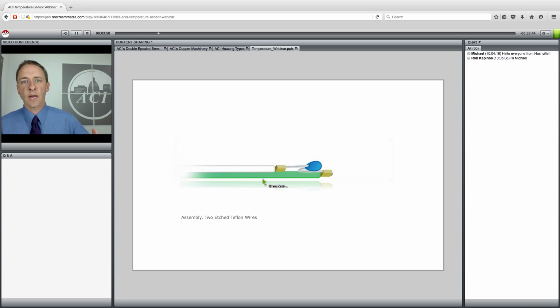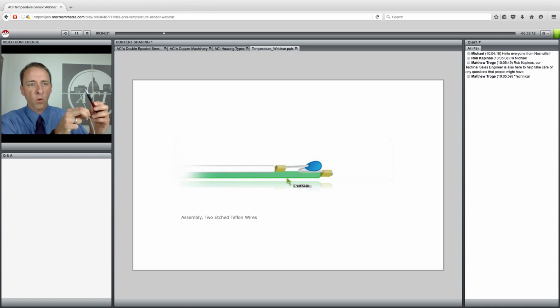And we also use a higher grade lead wire. It's an etched Teflon lead wire, compared to what a lot of other people are using, which is PVC. The Teflon wires are more thermally conductive, and so you get a faster response time than with a lower quality PVC wire. And we crimp that wire to the raw sensing element, and that creates a more secure connection and helps protect the very fragile raw thermistor. And you can see that this assembly is very small. It's less than the size of the tip of a pen.